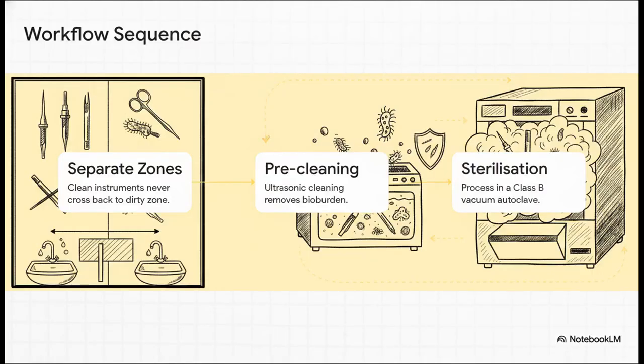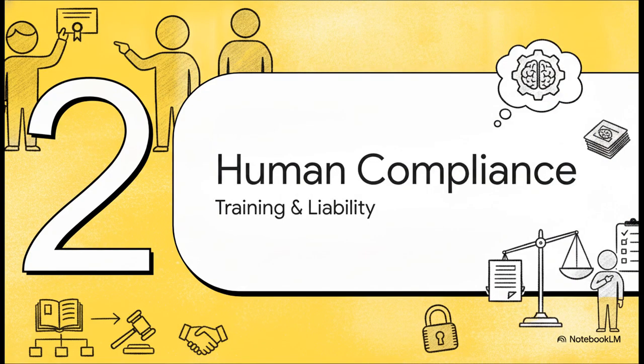But the machine alone isn't the whole story, right? The physical workflow matters immensely. Industry standards demand a strict, auditable sequence. Clean instruments must never, ever cross back through the dirty zone, and cleaning sinks absolutely have to be totally separate from hand-washing sinks. If you skip ultrasonic pre-cleaning, you leave behind bioburden, which is basically just organic matter, and that literally acts like a microscopic shield, protecting microorganisms from the steam of the autoclave. It's a massive risk. Moving right along to Section 2, Human Compliance.